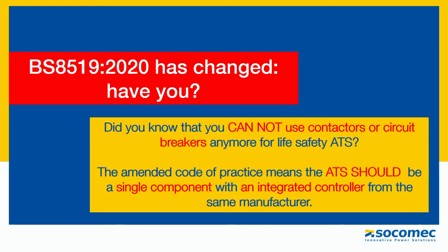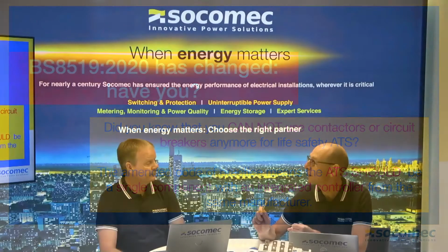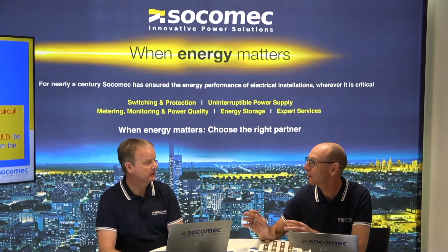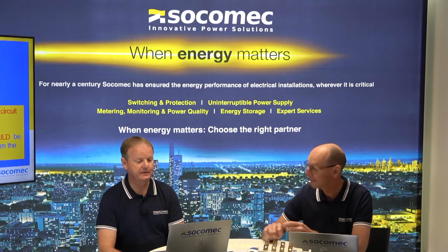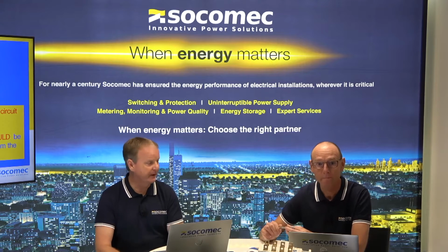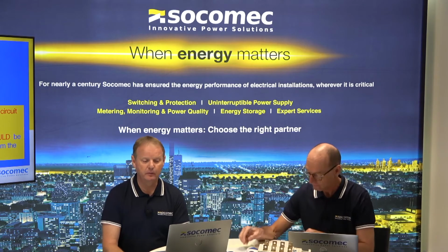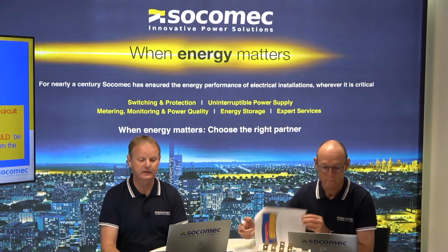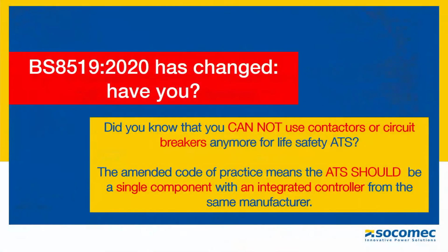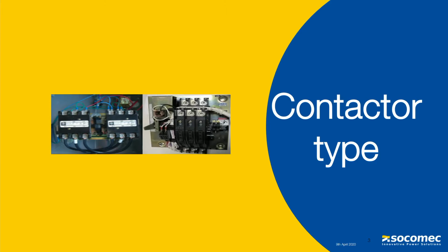The amended code of practice means that an ATS should be a single component with an integrated controller from the same manufacturer. I think a key point there, Michael, is that "should" in technical speak, or standard speak, is a "must". It's a must, yeah. So the "should" means you have to. They just use "should". So the major change, as you can see, is that you cannot use contactors or circuit breakers anymore. Here is a couple of examples of a contactor type transfer switch, and this is no longer allowed under BS 8519-2020.